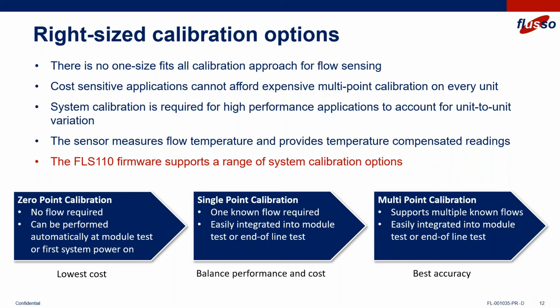The FLS110 firmware supports a whole range of system calibration options. From the lowest cost zero-point calibration, where no flow is required, that can be easily performed automatically at module test or first system power on, through single-point calibration, which we believe offers a great balance of performance and cost. Only a single known flow is required, and it can easily be integrated into end-of-line test where maybe you're running the motor in the product anyway. Or for a high precision application, we offer a full multi-point calibration, which supports multiple known flows, gives the best possible accuracy, and again is easily integrated into module test or end-of-line test.